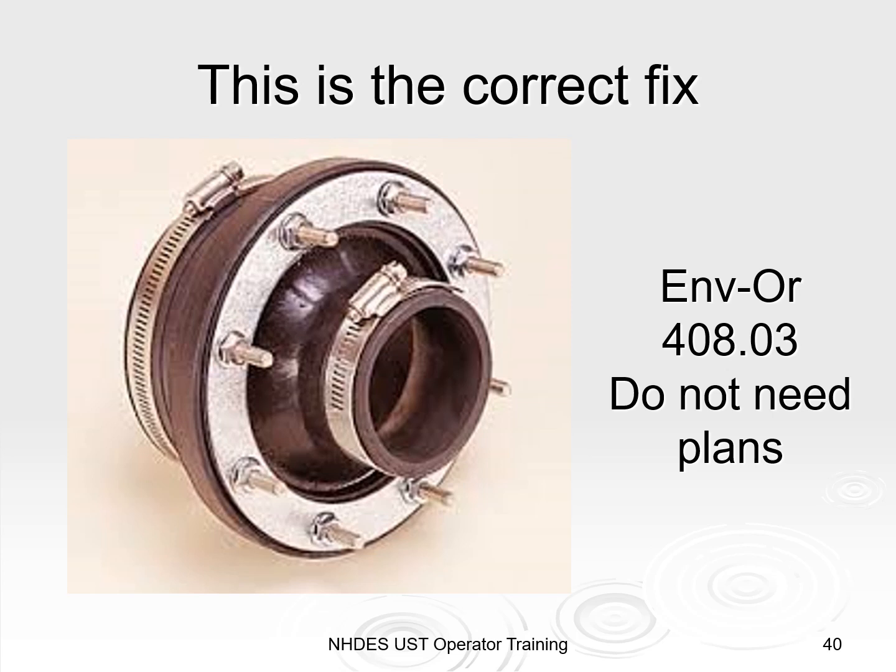This is the correct fix to the previous example. Env-Or 408.03 shows the requirements for replacements to piping or containment sumps. In this case, you do not need to submit PE-stamped plans to NHDES. You only have to submit the name and phone number of the certified tank installer who will be conducting the repair, written approval from the piping manufacturer, and a passing tightness test afterwards. This particular piping boot is from Bravo. It allows easy repairs to the entry boot on the wall of the piping sump without having to replace the whole piping sump — it works off a compression seal and all bolts are tightened against the sump wall.